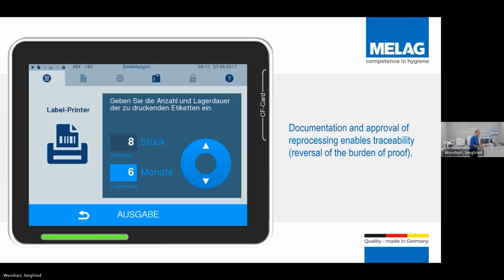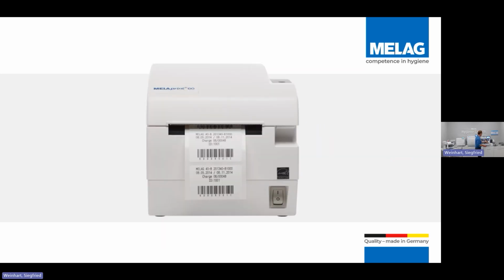And at that point, the unit will then ask you, how many of these little labels do you want for the pouches that you've got inside there? So for future sake, I've put 10 pouches in there. So I want 10 labels, okay? So I'll put in 10 and then press the button, and it'll print out those 10. What happens then is these little labels get printed out of the barcode label printer, and they will have the sterilization date and the expiry date on there, which you can see in the bottom line, the second from the top line. It'll have the model, it'll have the serial number, and it'll have who released it, that code as well.